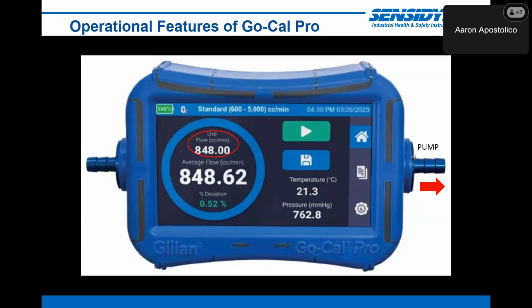In this circled feature, you see the live flow reading. This is really helpful in making quick adjustments to your air sampling pump. So you're not waiting for a cycle or a bubble or a dry cell puck to move up and down. You get an instantaneous reading.